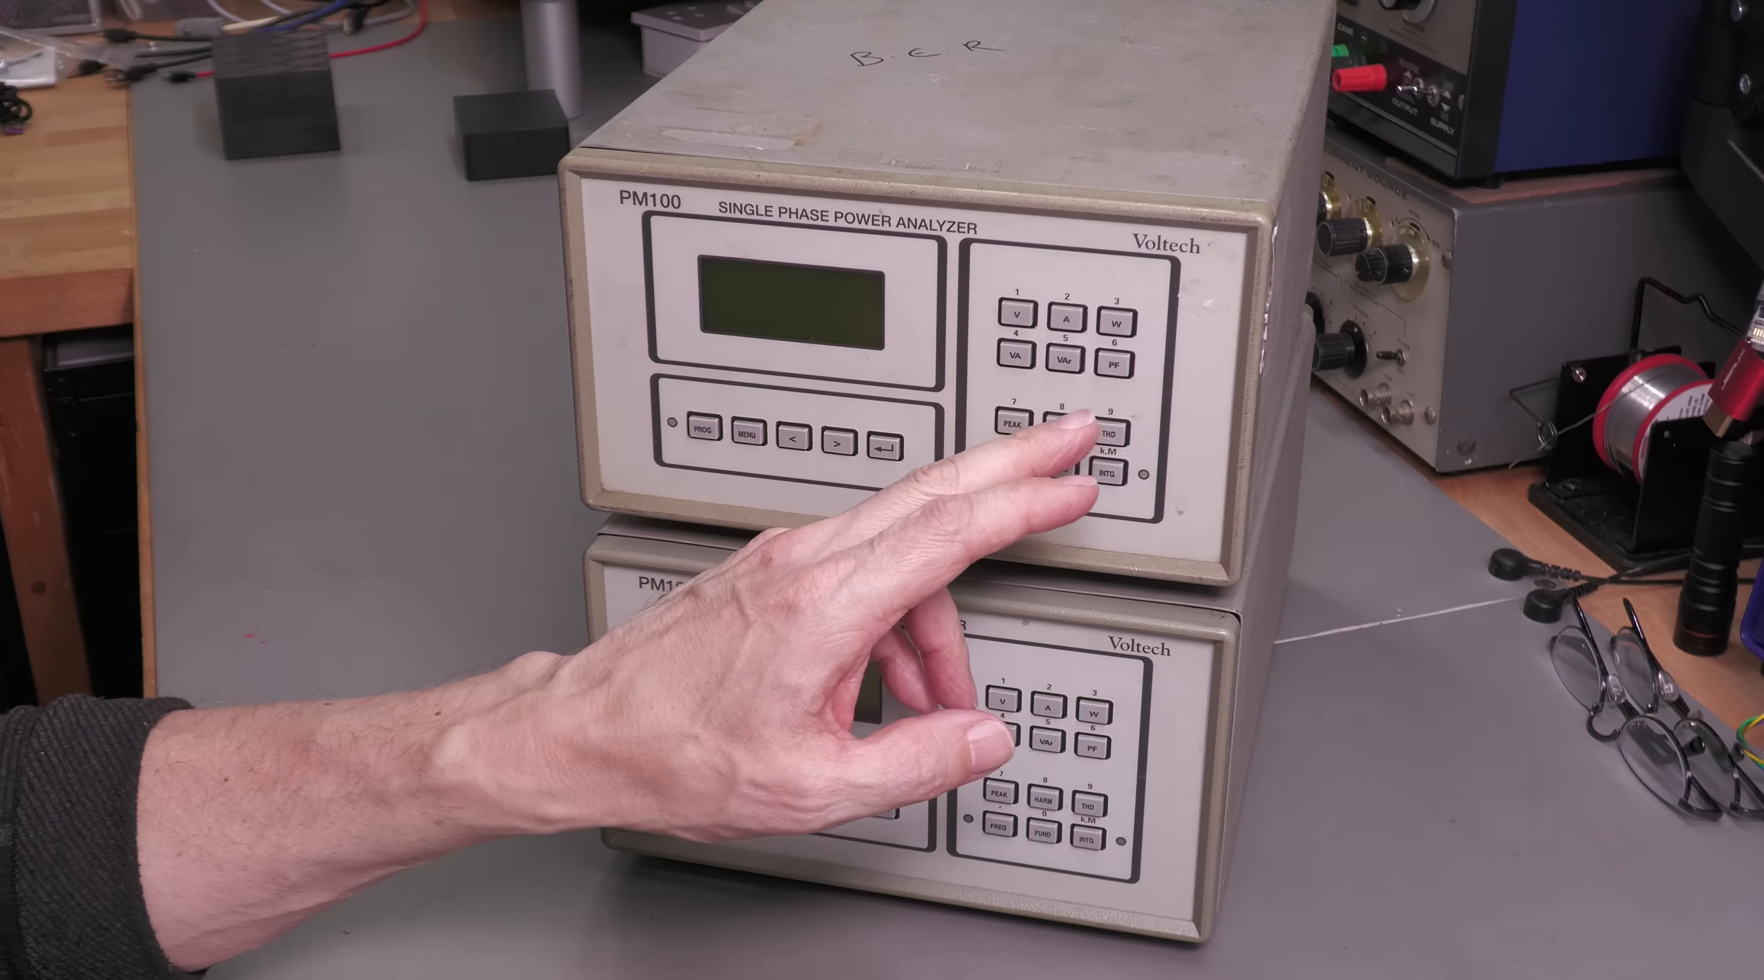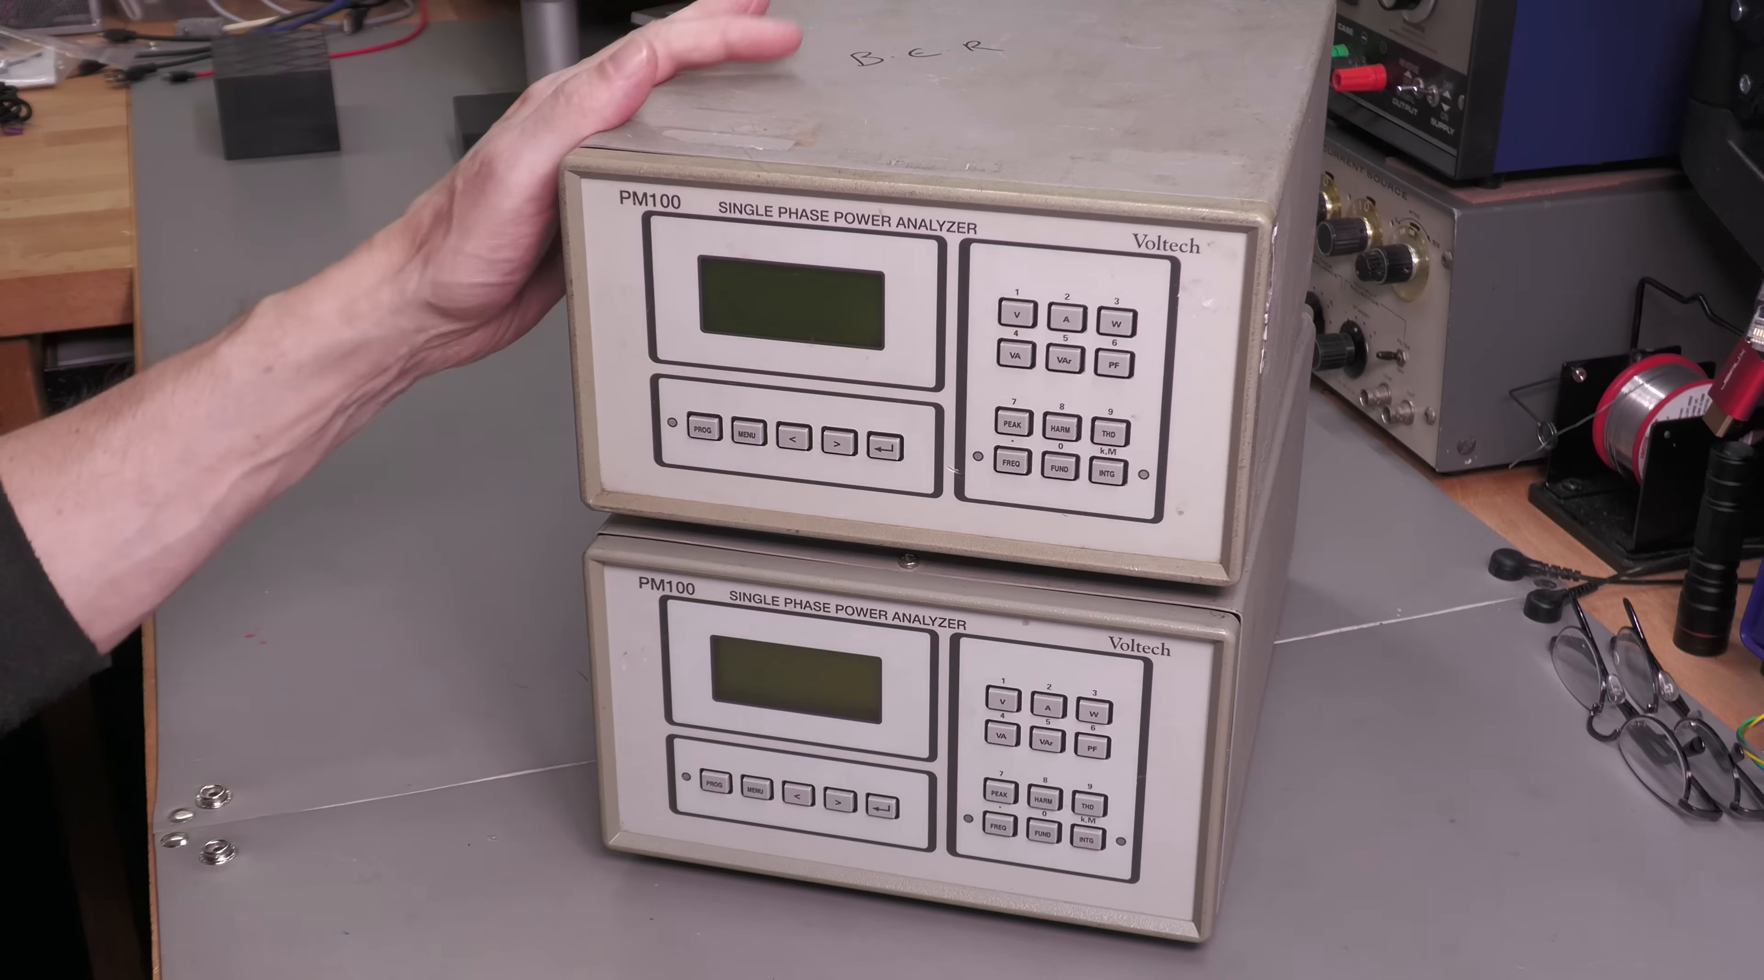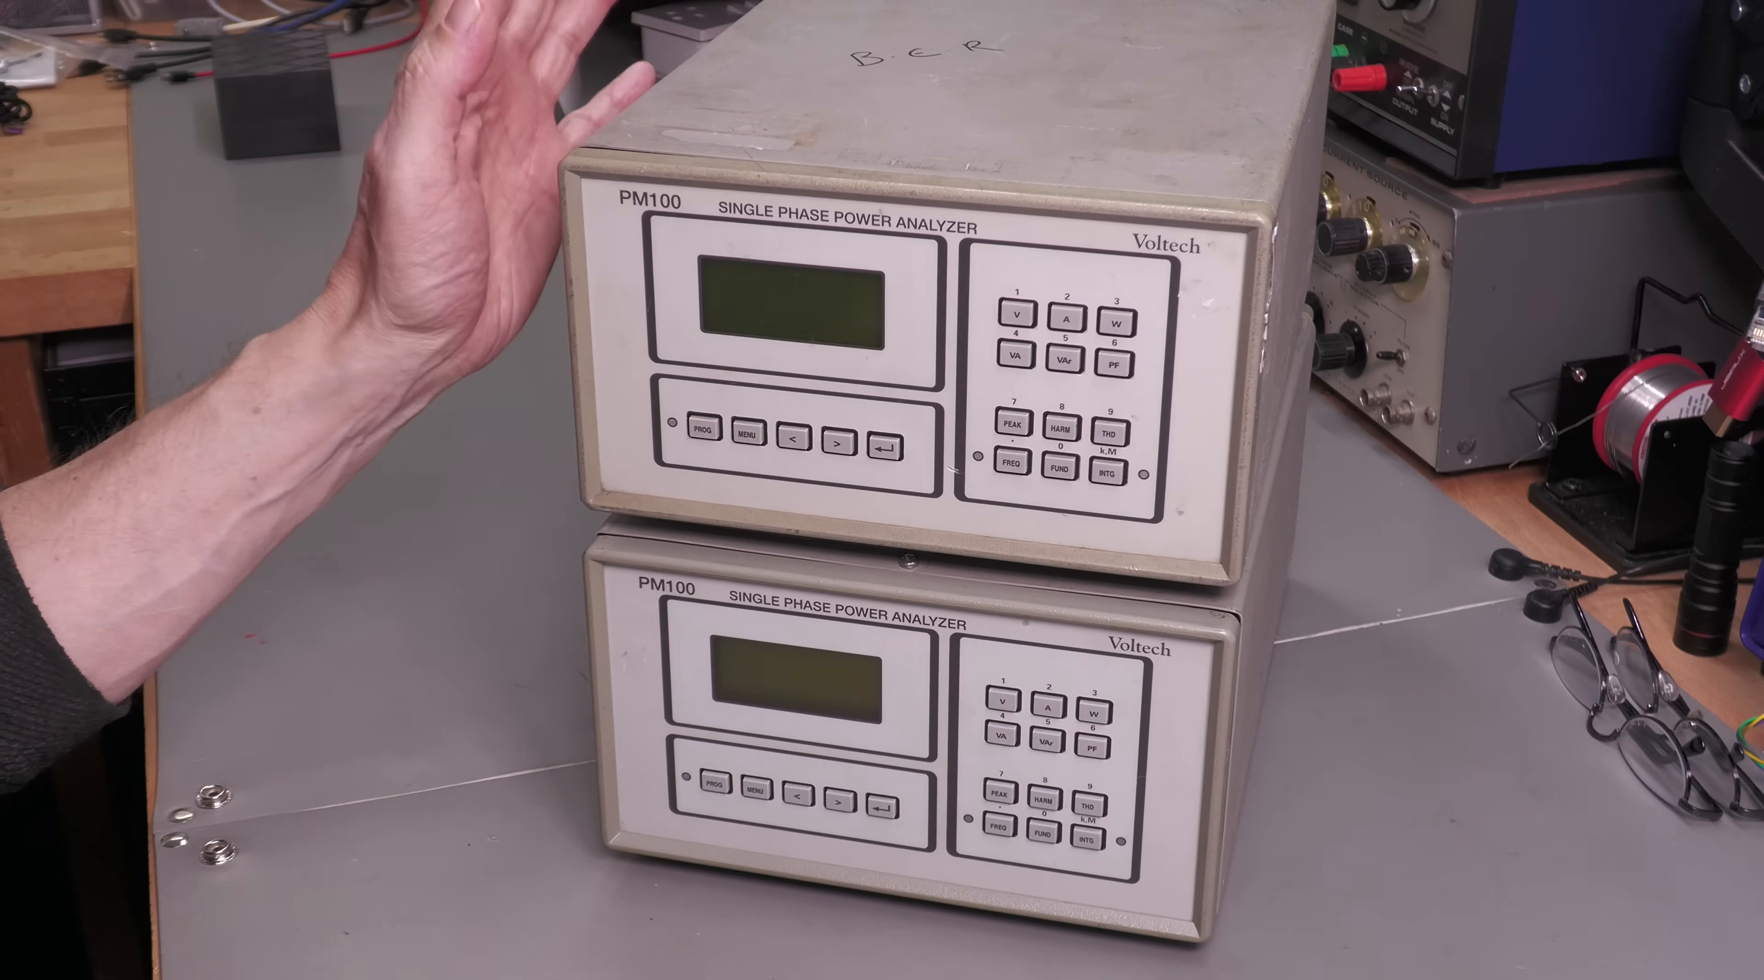VA, VAR, power factor. On the display here you've got all sorts of character-based data, and you can set the unit up to measure peaks, to integrate data for the likes of watt hours or VA hours, etc.